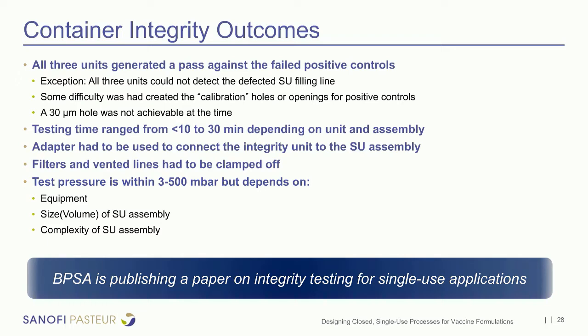The filters and the vented lines had to be clamped off, which is one of the limitations of the machine, is how those are clamped off using hemostats or C-clamps, how far you tighten those. It can create a limitation because you're not testing anything downstream of that clamp, and you have to make sure that the clamp is done in such a way that it's not leaking itself. In some cases, the lines were sealed off, so it wasn't a problem. The test pressure was within 3 to 500 millibars, but of course this depends on the equipment, the size or volume of the single-use assembly, and the complexity of the assembly. I should note, Alain Porras, who's speaking next, has been leading the authoring of a paper on integrity testing for single-use applications as part of the BPSA.